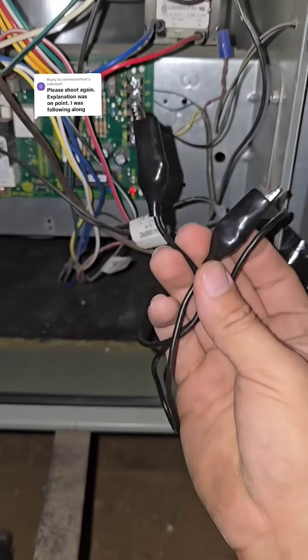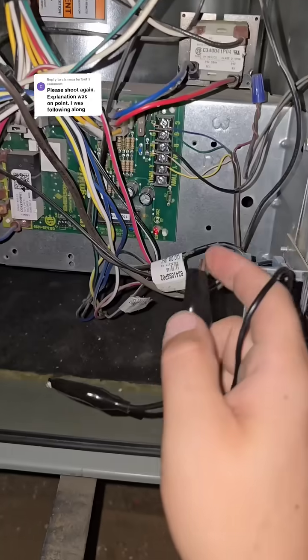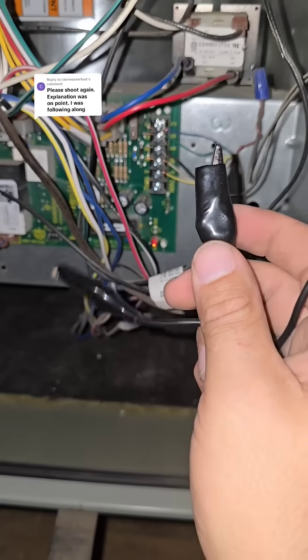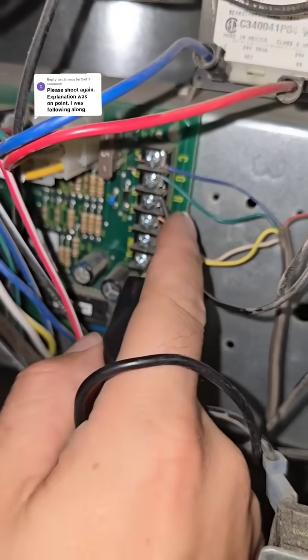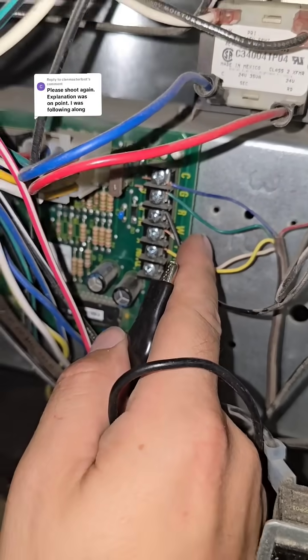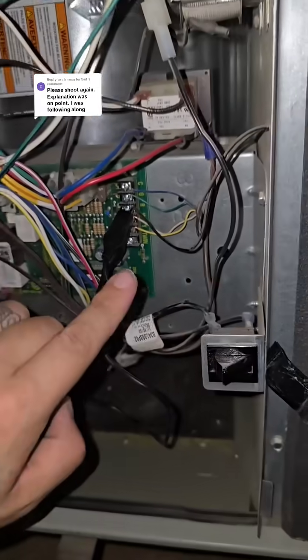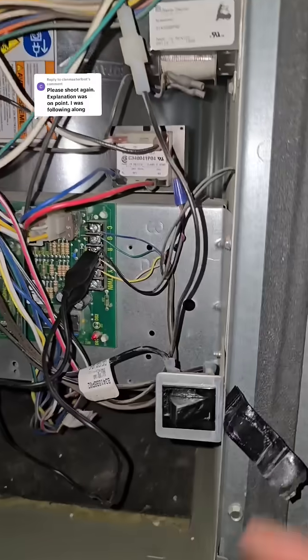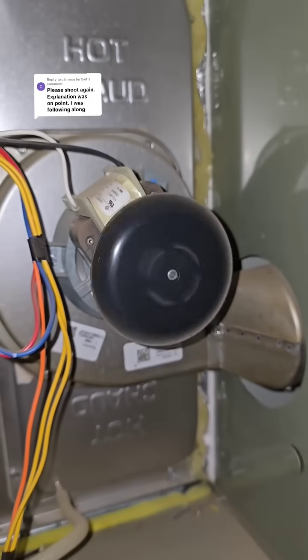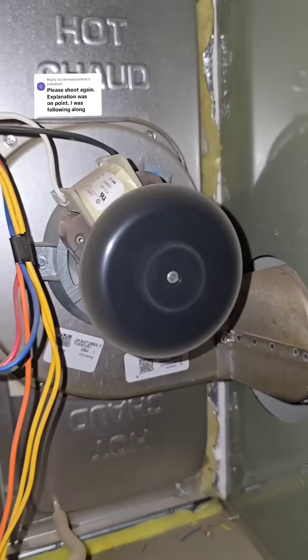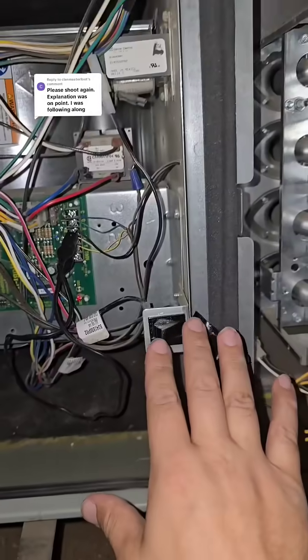I got this little jumper wire. I'm going to bypass the thermostat. We're going to put the system in heating mode. So we're going to put one end on R and one end on W. Just like that. So now it's calling for heat. So when I push this button in, it should make this inducer motor spin. Once this inducer motor spins, I'm going to go ahead and let off power.